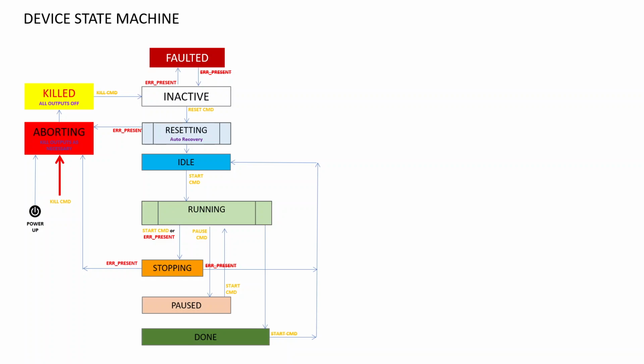So we'll typically hold ourselves in a killed state as long as the e-stops are active. When we want to start running a machine, a device, we have to go through a resetting step. In a resetting step, we're doing things like initializing data, initializing outputs, typically based on either the part data or some sensor information. But effectively, we're getting ourselves ready to be run.